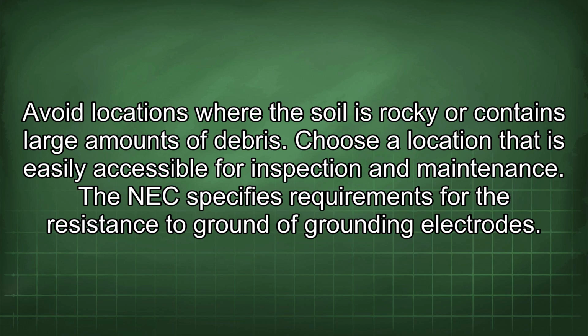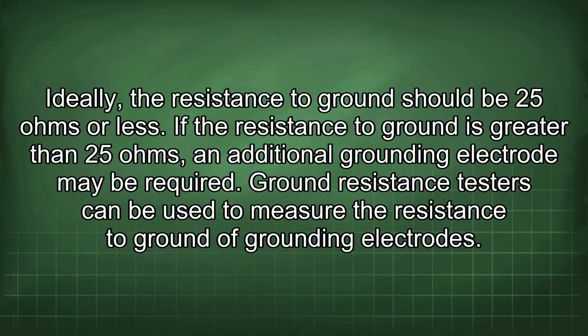The NEC specifies requirements for the resistance to ground of grounding electrodes. Ideally, the resistance to ground should be 25 ohms or less. If the resistance to ground is greater than 25 ohms, an additional grounding electrode may be required.